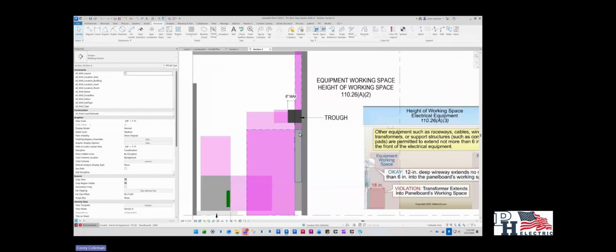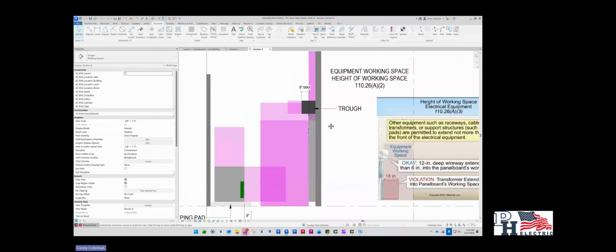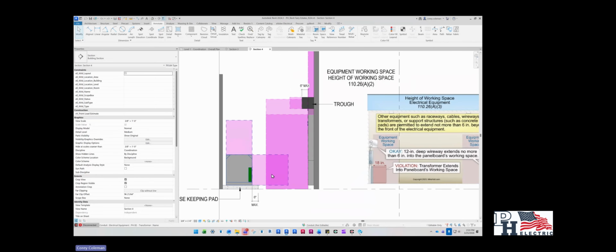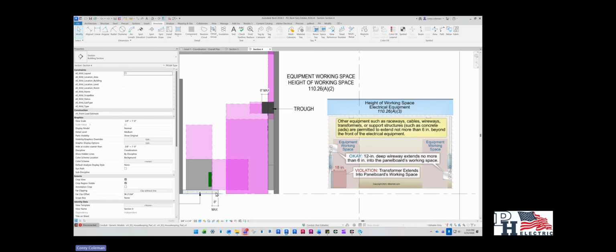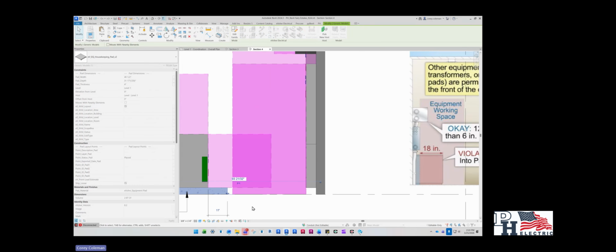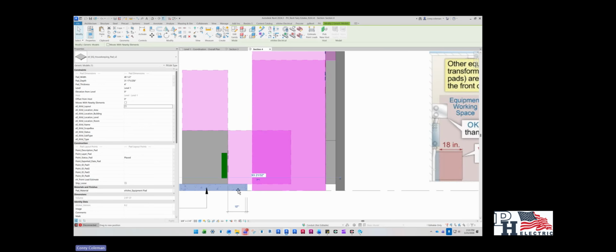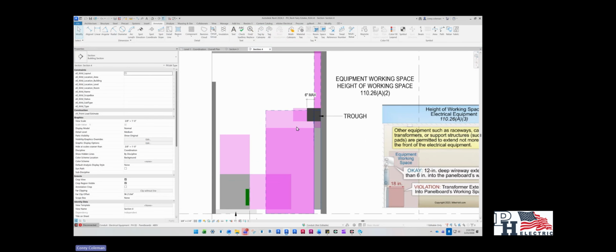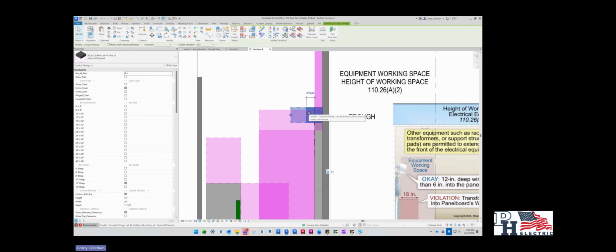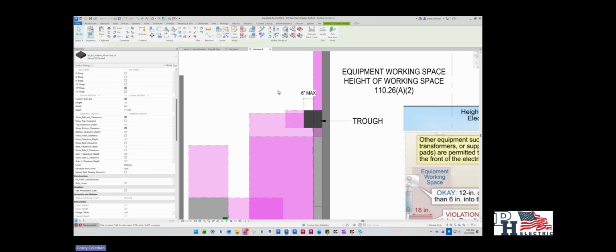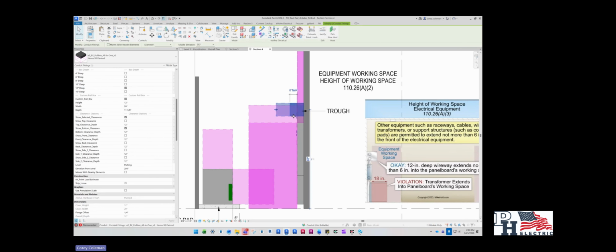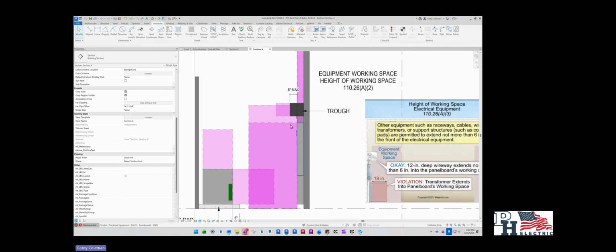You can also have electrical equipment and housekeeping pads extend 6 inches into that working zone if you need to, but 6 inches is max. If you have anything further than that, say this housekeeping pad is 7 inches or even further, that would be against code and you might get called out on it. Same thing with the trough: if you went into a larger trough size, not 12 by 12, but like 18 by 18 for whatever reason, that would be sticking too far into the working space clearance.